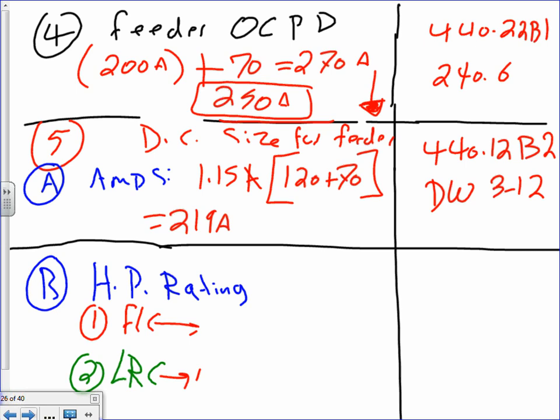What's your next standard for 219? Do I have 300 disconnects? Disconnects, remember, this one goes up. Yeah, this one goes up. So I have to go to 400. So my next standard is 400 amps. Now this one, like you said, we go up. Disconnects will always go up. 400. So that's it in terms of the disconnect amp size.